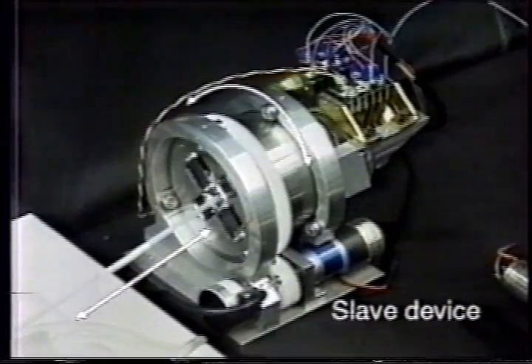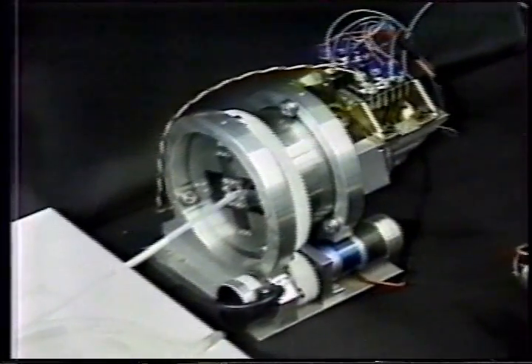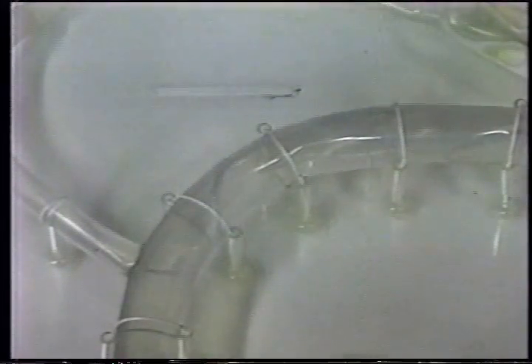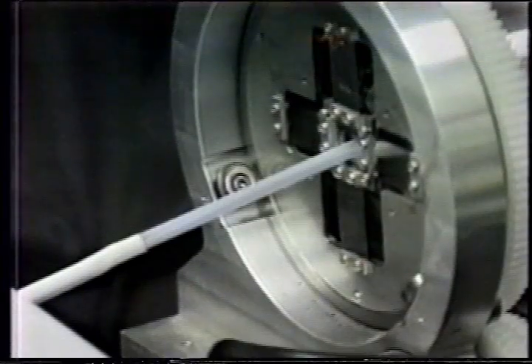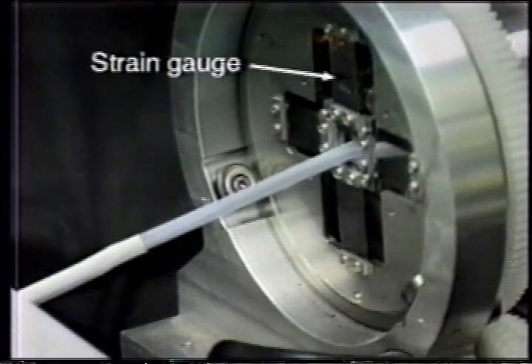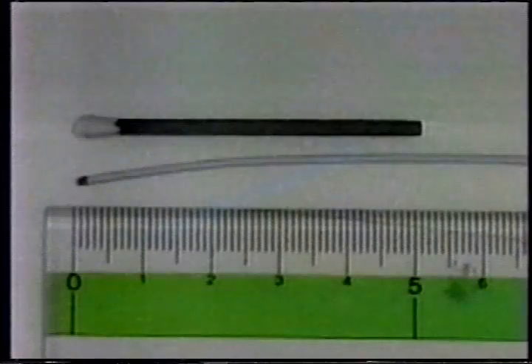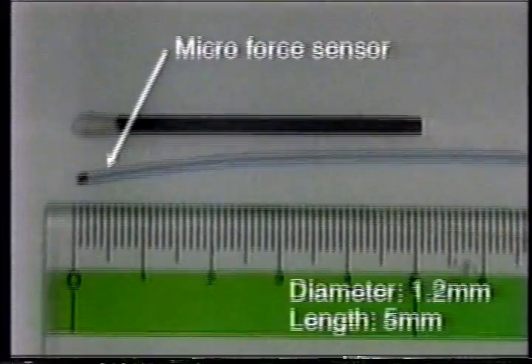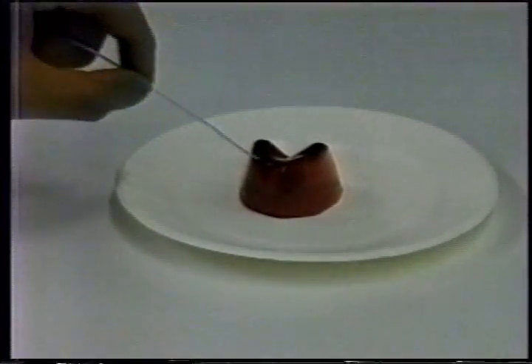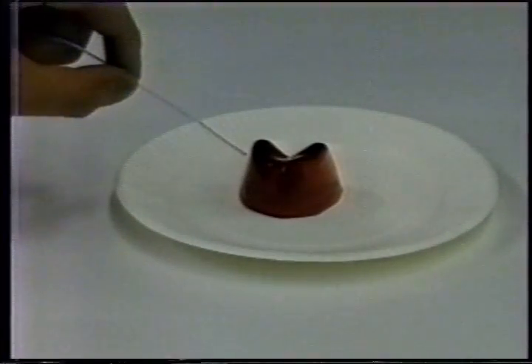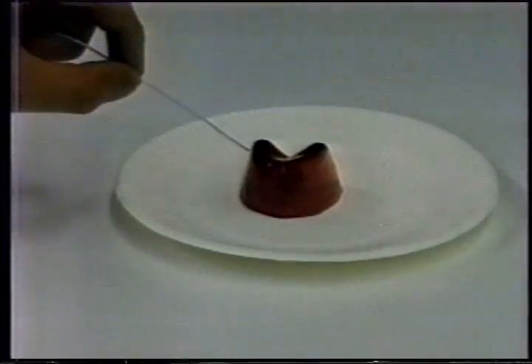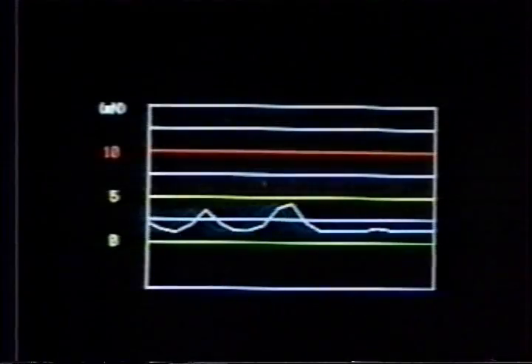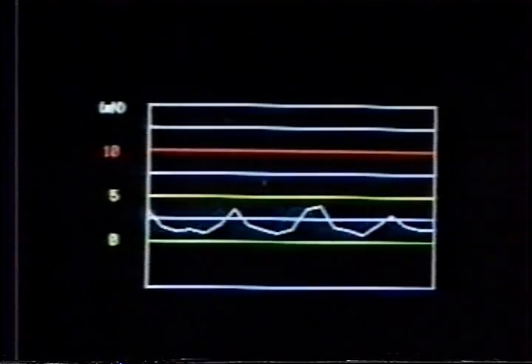The slave device handles the catheter. An inner unit is suspended by a set of thin beams from the outer shell. There is a pair of rollers which clutches the catheter in the inner unit. When the catheter side contacts the blood vessel wall, a strain gauge force sensor in the slave device measures the contact force. A microforce sensor is installed to measure the force generated between the catheter tip and the blood vessel wall. The diameter of the microforce sensor is 1.2 mm and the resolution is 0.5 millinewton.